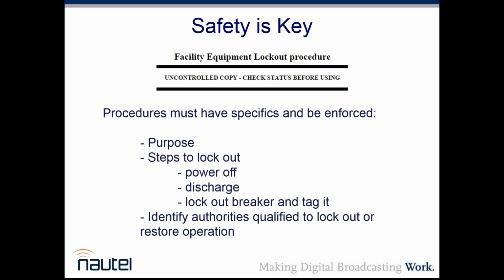Again, this is one of our in-house procedures, but once you write these procedures, they have to be enforced. You have to document the steps to do the lockout, whether it's power off, discharge stuff, lock the breaker, and tag it. Over and above that, you should have a list of the people who are actually qualified to restore operation. Typically, you're not going to want the IT guy bringing up power to a 30-year-old CCA or an old tube rig.